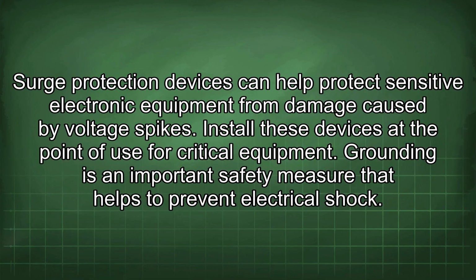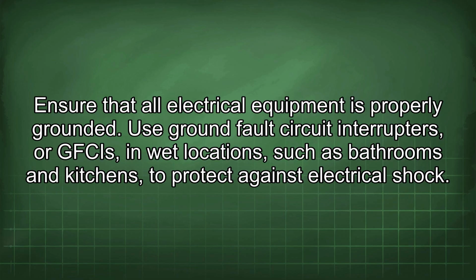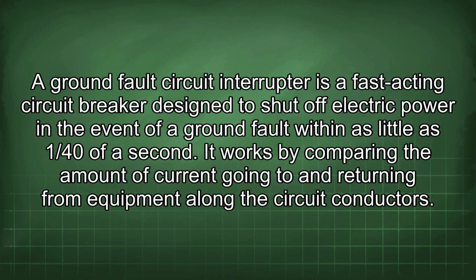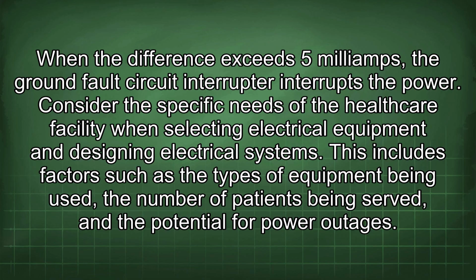Grounding is an important safety measure that helps to prevent electrical shock. Ensure that all electrical equipment is properly grounded. Use ground fault circuit interrupters, or GFCIs, in wet locations, such as bathrooms and kitchens, to protect against electrical shock. A ground fault circuit interrupter is a fast-acting circuit breaker designed to shut off electric power in the event of a ground fault within as little as 1/40 of a second. It works by comparing the amount of current going to and returning from equipment along the circuit conductors. When the difference exceeds 5 milliamps, the ground fault circuit interrupter interrupts the power.